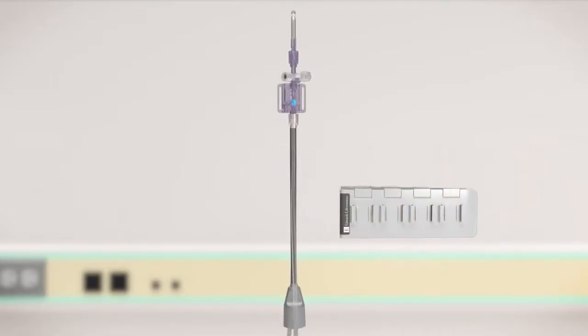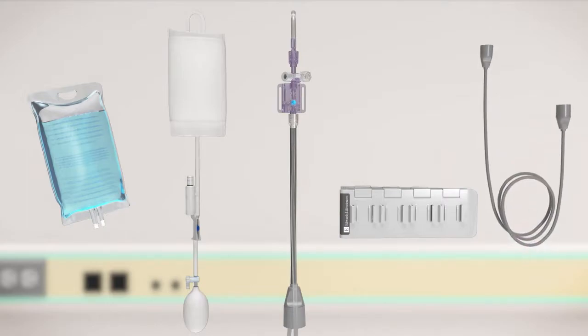Here's what you will need to get started: one TruClip holder or an arm mount strip, a 500 or 1000 milliliter normal saline IV bag, a properly sized IV bag pressure cuff, and appropriate cable that connects your bedside patient monitor to the TruWave transducer.